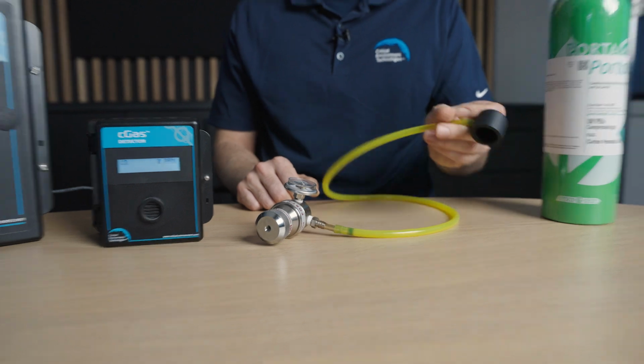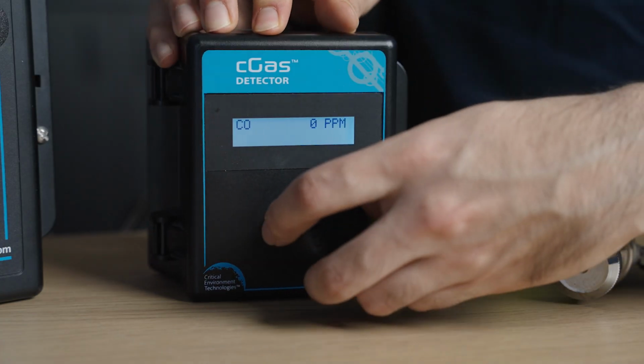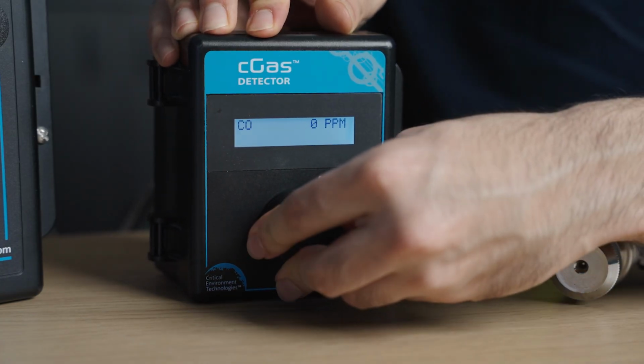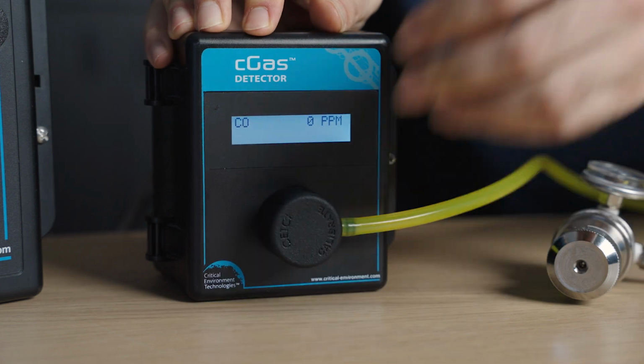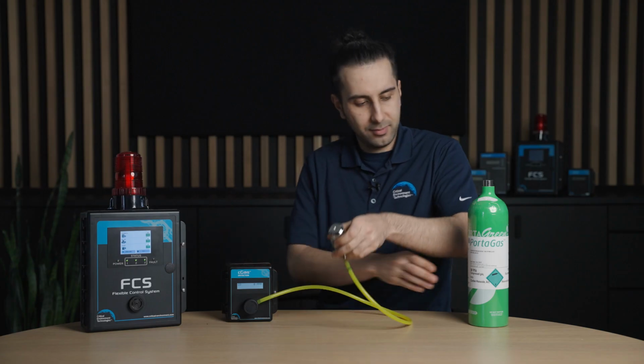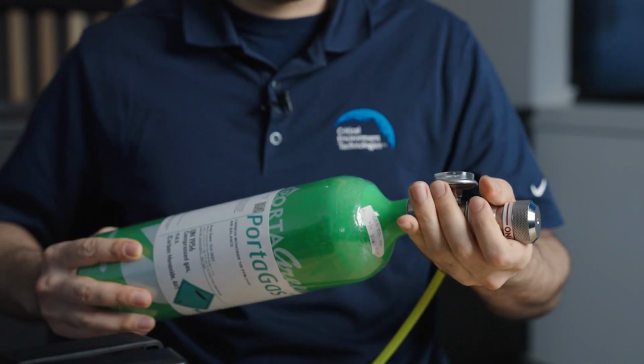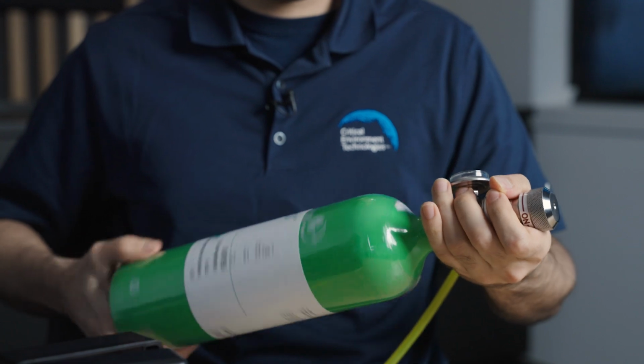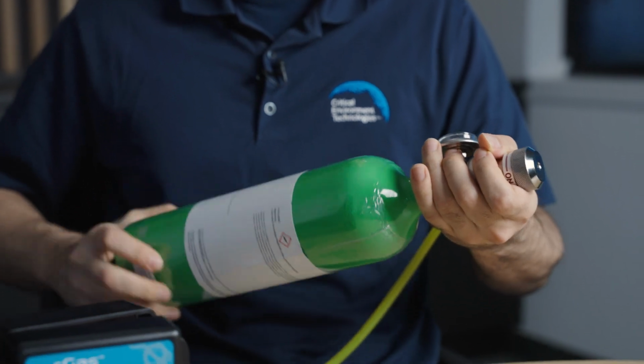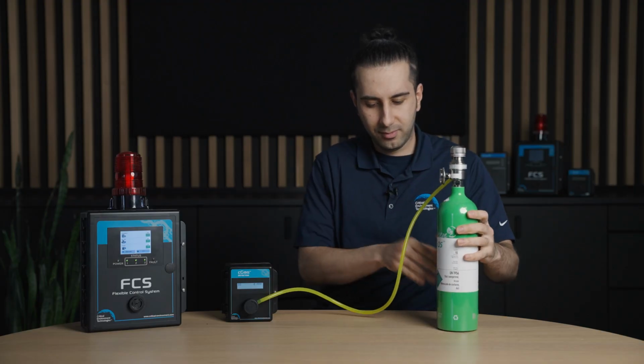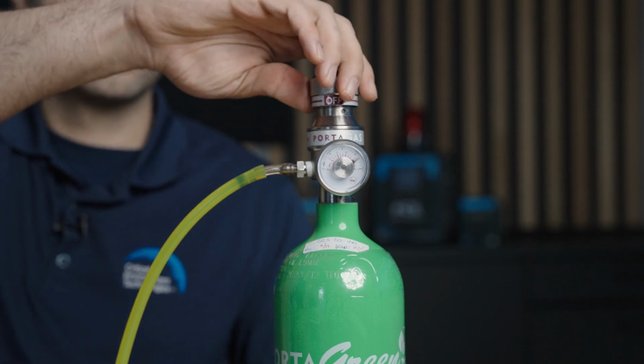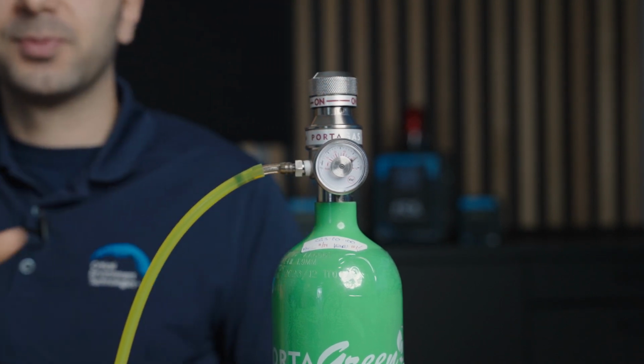To begin the bump test, first connect the calibration gas cylinder to the detector using the tubing and the calibration clip. I'm using the 100 ppm carbon monoxide span gas to match our sensor and target gas. Open the valve on the regulator to allow the gas to flow.